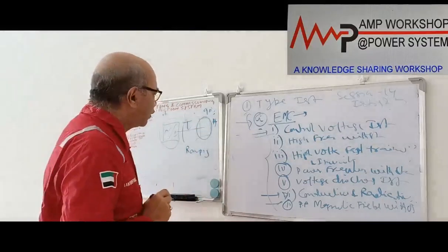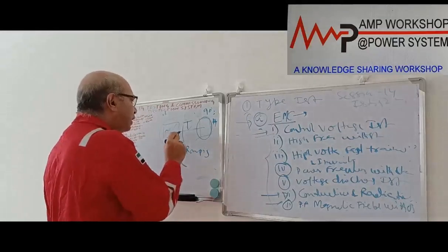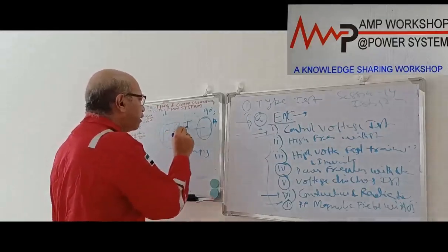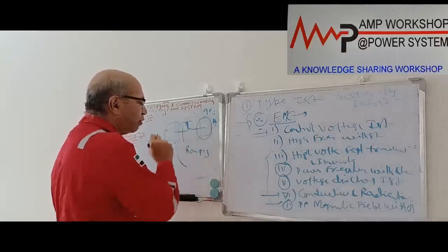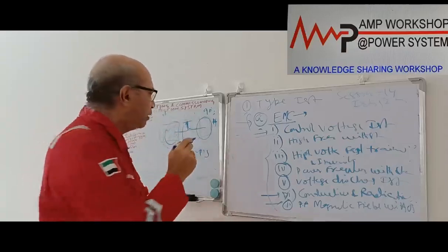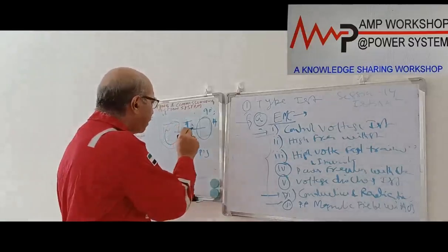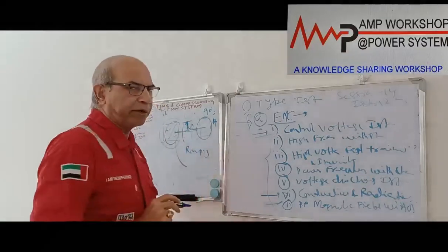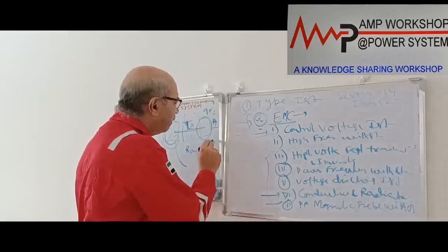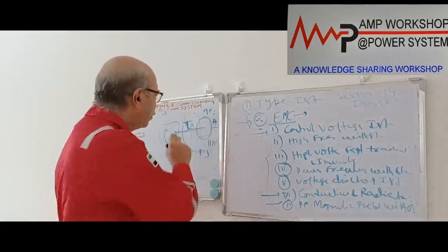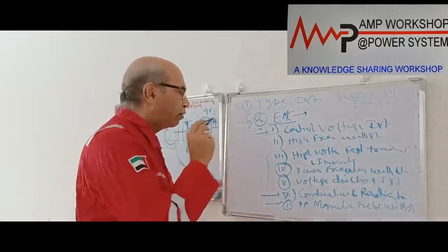That is one thing. Similarly, when the power comes back, then immediately what will happen? As the battery got discharged, it will try to charge the battery. But supply will be coming from the battery till it is reaching the control voltage. During that ramp up, during the charging stage, we call it ramp up. During ramp up, if the supply is coming from the battery or from the charger, the relay should not mal-operate. That means if the setting has 90%, the relay should not operate. If the setting is at 110%, the relay should operate. So that is what we check with this control supply. So these are the three tests we carry out on the control supply.